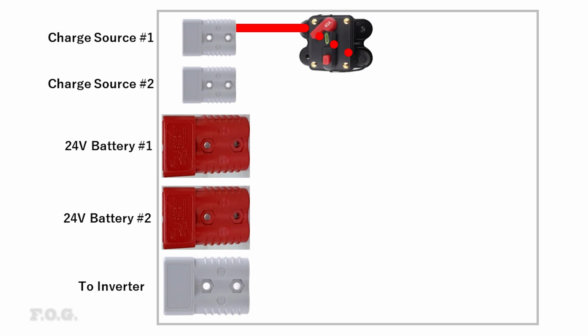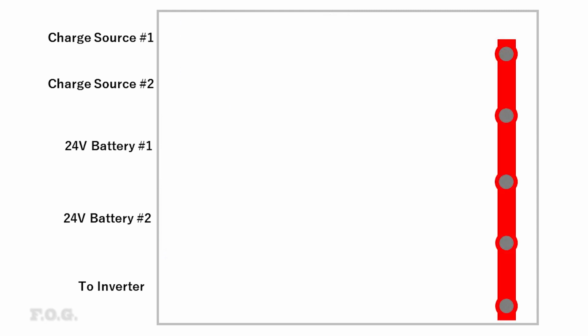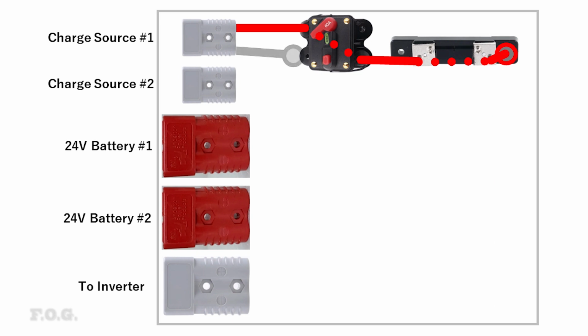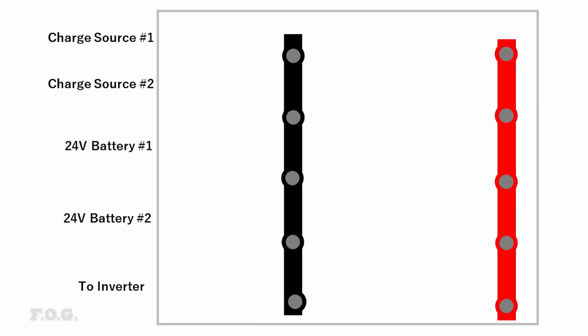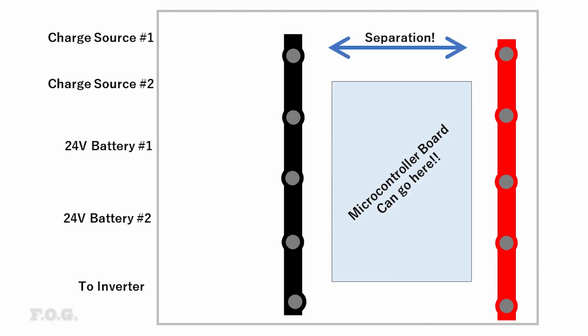The positive rail for each connector passes through the isolation switch, then through the shunt before connecting to the positive bus bar, located on the other side of the panel. The negative rail is connected as directly as possible to the negative bus bar, also on the other side of the panel. Doing it this way means that on the back of the panel, there's a good amount of distance between the positive and negative bus bars.